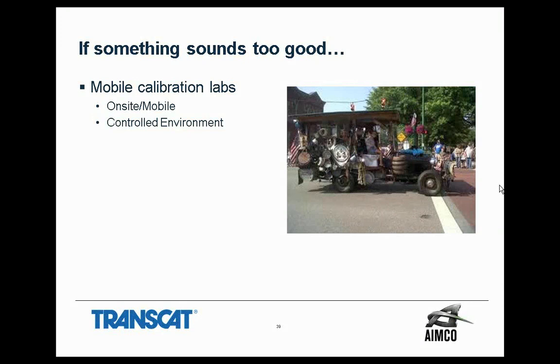Real quick, if you think about how gauges are typically calibrated, you use deadweight testers. So for a mobile calibration or an on-site, we have to load that up, put it in a truck, drive 3 hours out into Tehachapi. You're in the mountains, a lot of dust, the thing's been bouncing around for us. How do we know that that deadweight tester is in calibration when it arrives?